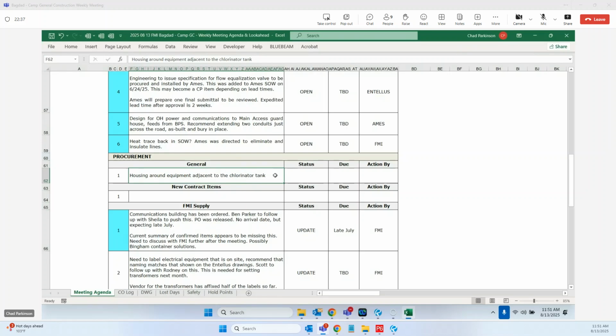So the chlorine analyzer that's mounted on that board, we ended up having to, after we got the shop drawings, add another device that measures the flow that the chlorine analyzer measures, and that board got bigger and bigger. So I issued a field directive that showed the bigger board for mounting the chlorine analyzer and the additional equipment needed to measure the flow in the chlorine analyzer. I hope that makes some sense.